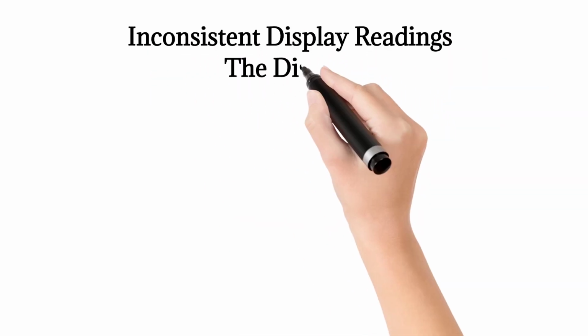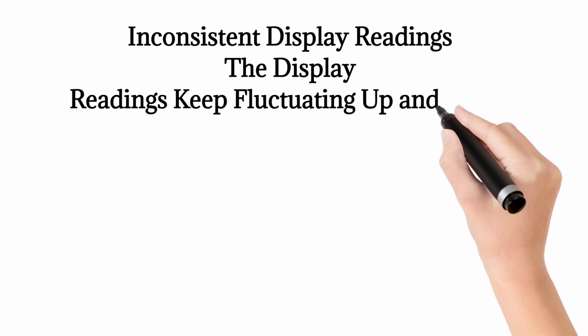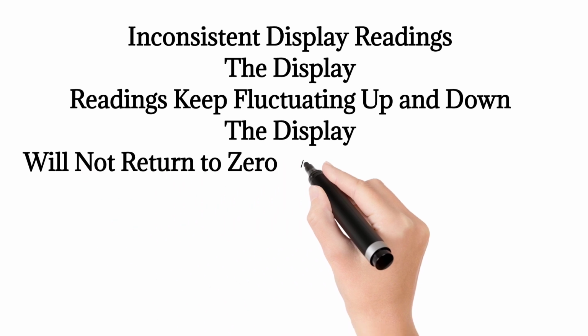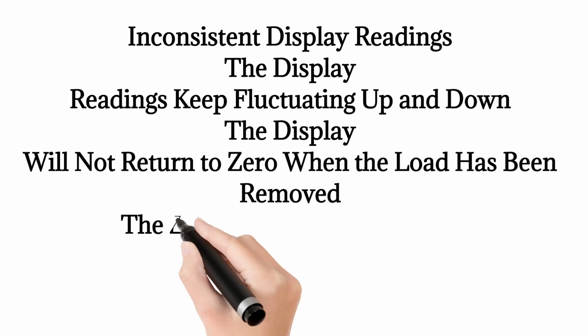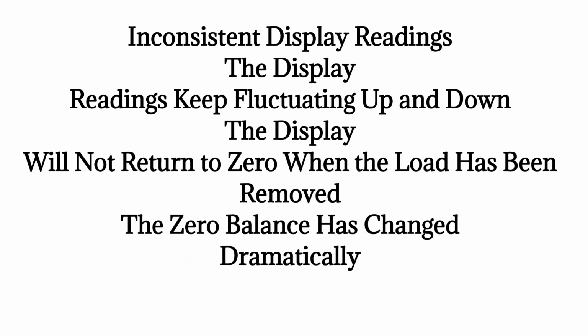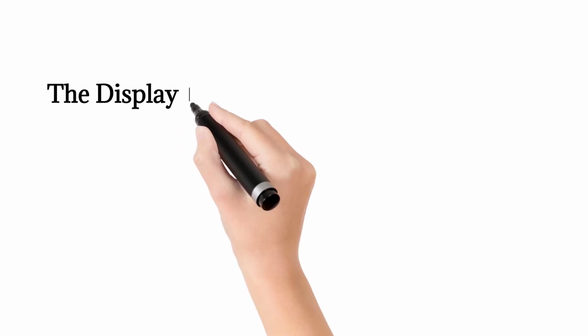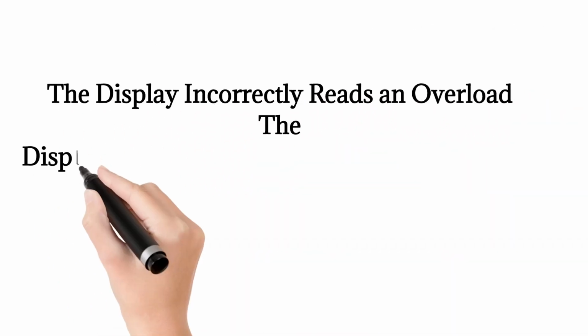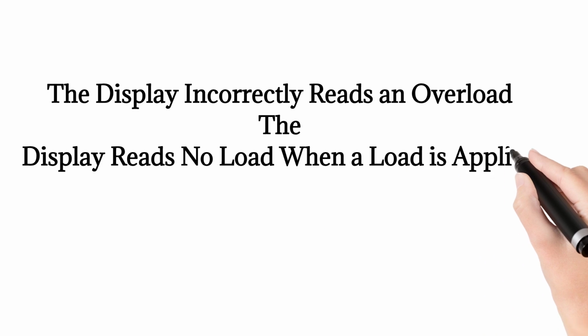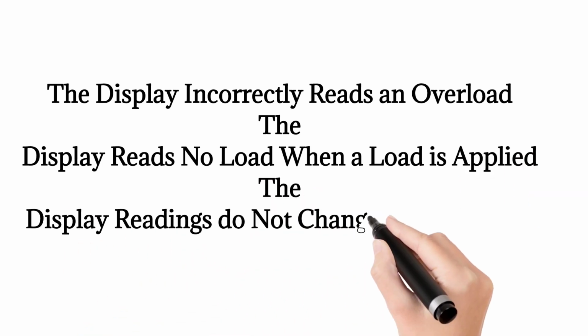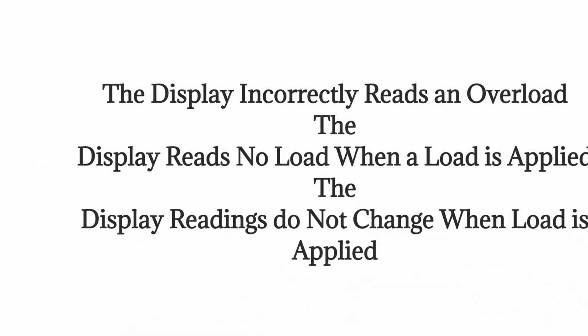Inconsistent display readings. The display readings keep fluctuating up and down. The display will not return to zero when the load has been removed. The zero balance has changed dramatically. The display incorrectly reads an overload. The display reads no load when a load is applied. The display readings do not change when load is applied.